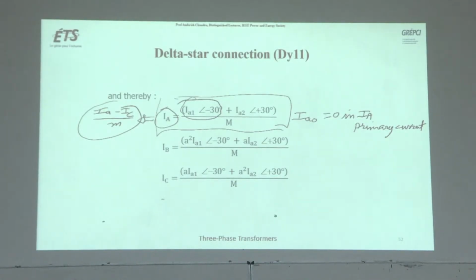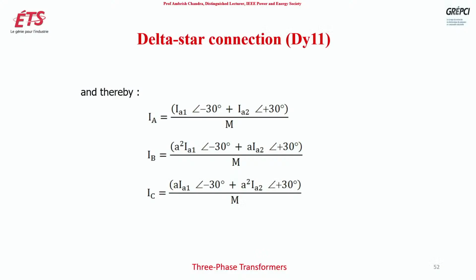positive sequence current, if you on the secondary side, when you bring it to the primary side of that transformer, it will get a phase shift of minus 30 degree. And if you have a negative sequence current on the secondary side and you bring it to the primary side, IA capital, then you will have positive plus 30 degree phase shift. This is very important to know, because we know seventh harmonic is what? Positive sequence. And fifth harmonic is a negative sequence.